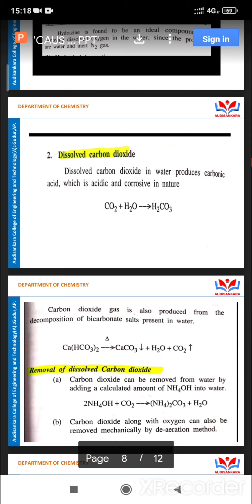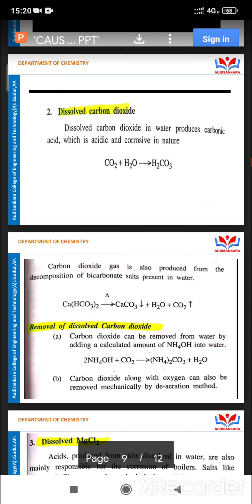Carbon dioxide has one more source: bicarbonates. Whenever we heat the water, the bicarbonate of calcium is dissociated into CaCO3 + H2O + CO2. The CO2 again reacts with water to develop carbonic acid, which is the main cause of corrosion in the boiler. We can remove CO2 by adding a calculated amount of NH4OH, ammonium hydroxide, to water. NH4OH reacts with CO2 to give (NH4)2CO3 + H2O. The carbon dioxide is completely blocked, and diammonium carbonate is formed.